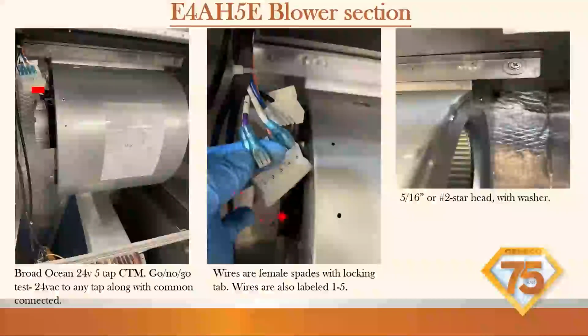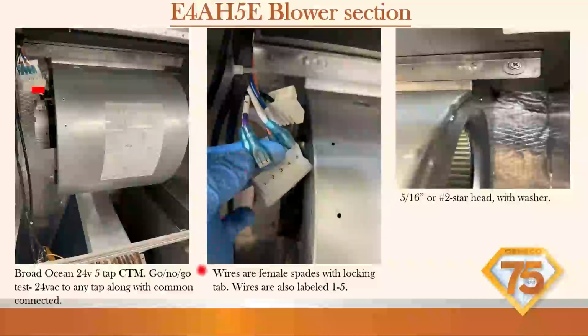Blower section. Again, these are pretty easy to get to. It's got the 24-volt 5-tap, which we're going to make these settings via dip switches, and I'll show you that later. Apply 24-volt to any tap with common connected. So for a go, no-go test, we can apply 24-volt to any of these tap speeds, and we should get the blower motor to go. If the blower motor does not go with 24-volt applied, and you have 220 going to it too, then it's a bad blower motor. So that's a good no-go test. Keep that in mind. Apply 24-volt to one of those connections, and your blower motor should go.